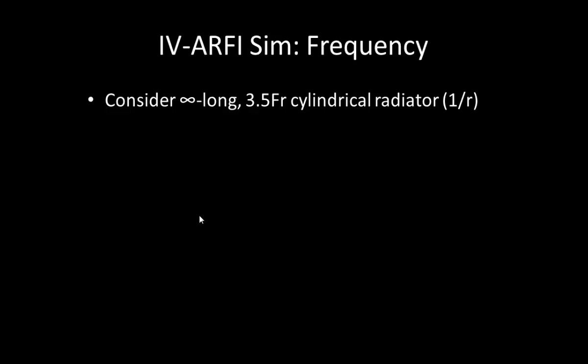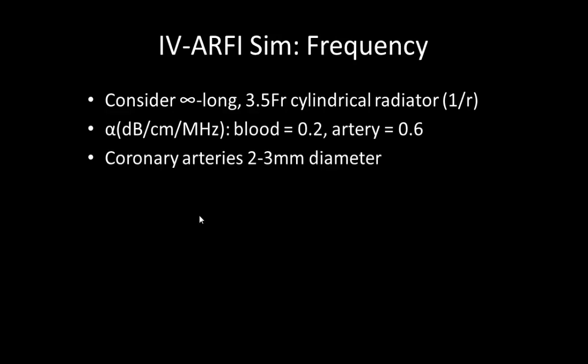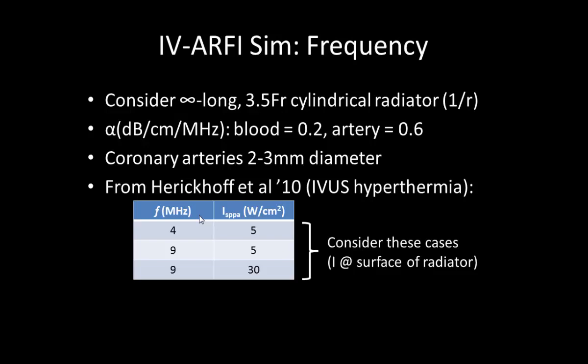Regarding frequency, we first considered a 3.5 French cylindrical radiator of infinite length and noted that a cylindrical wavefront falls off as 1 over r without attenuation. We then considered attenuation in blood and the arterial wall, and the fact that coronary arteries are two to three millimeters in diameter. We considered three cases first investigated related to IVUS hyperthermia, taking those intensity values at those frequencies as our initial cases. From here we could calculate the body force F as a function of radial distance R and frequency, for both two-millimeter and three-millimeter diameter vessels — six cases total.